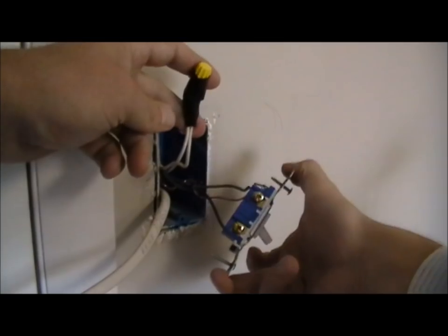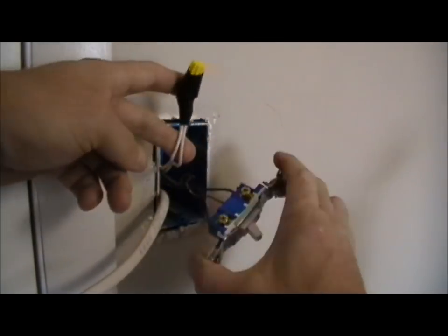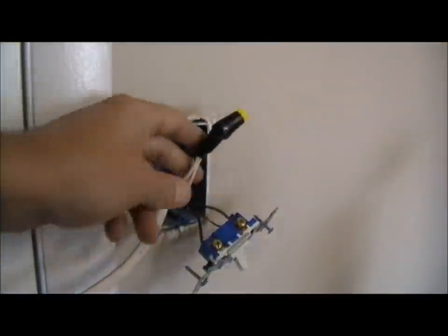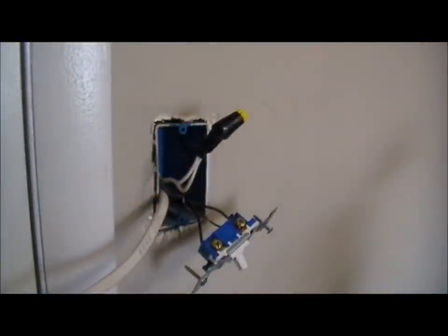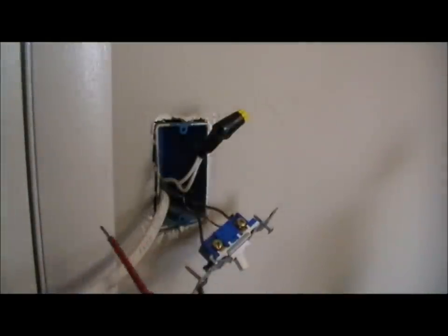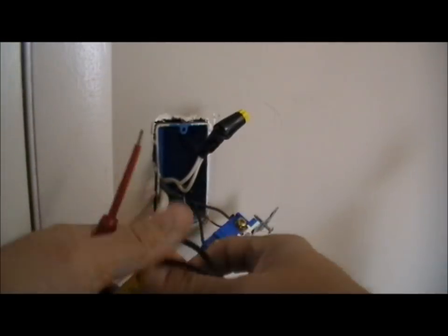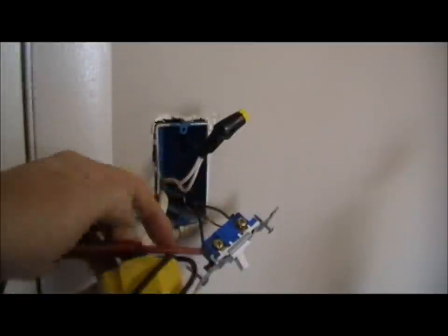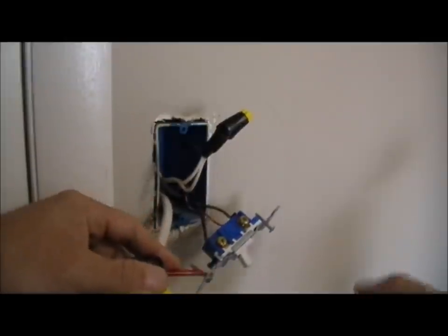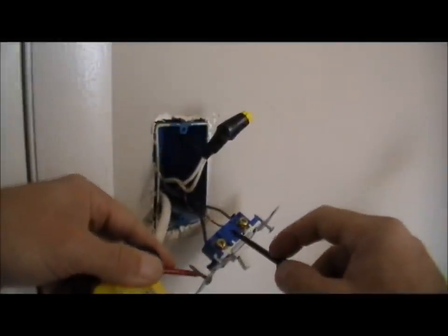Inside the wire we have two conductors. We have black conductors and white conductors. The white conductors are our neutrals. They're under this wire right here. And the black conductors, one black brings the hot in and the other black brings the hot out. If we use a tester, here's kind of an old tester, but it works just fine. We're going to put one of the tester leads on the yoke, which is grounded, and one on the hot wires.